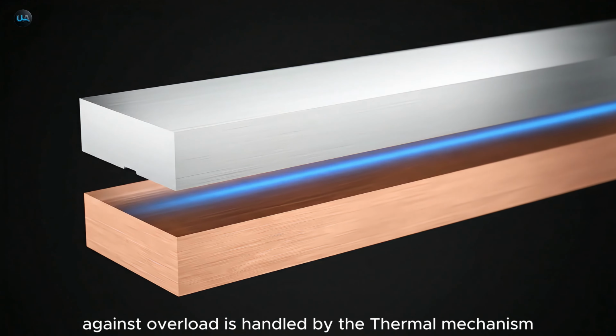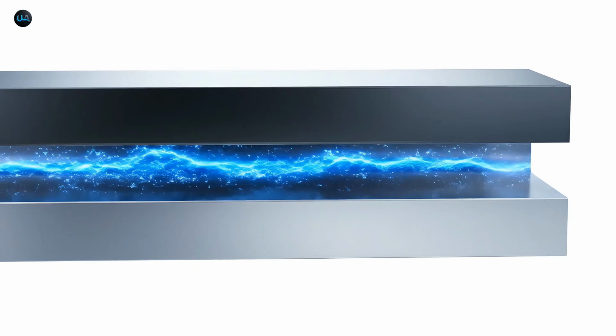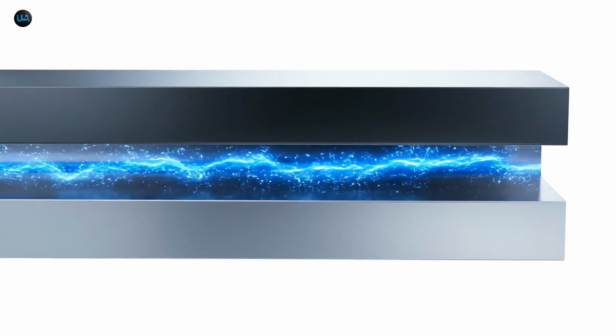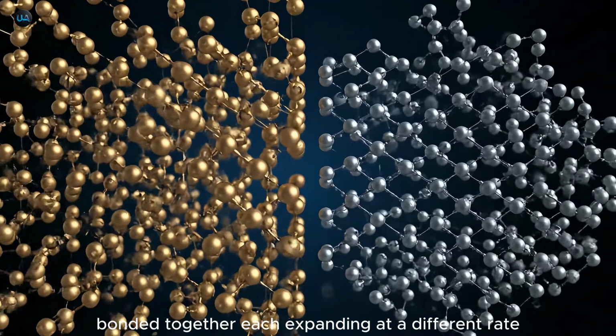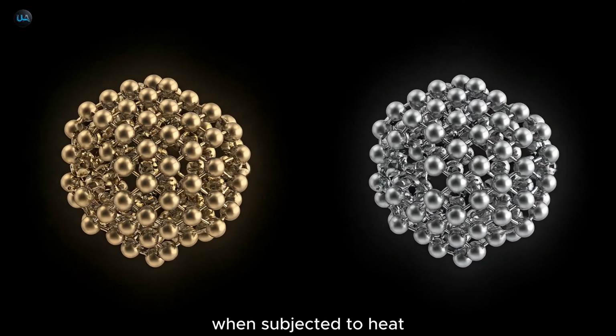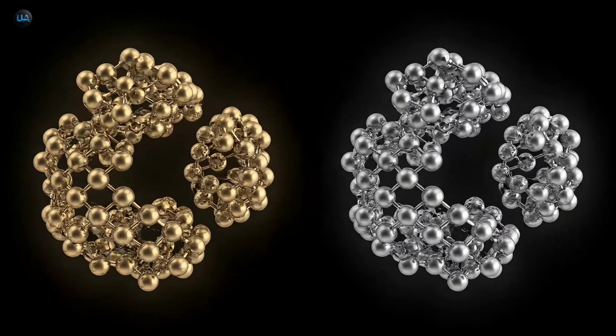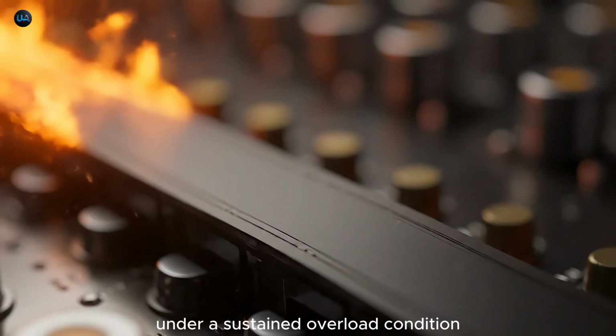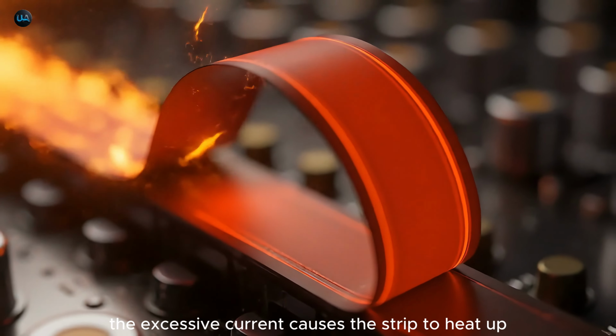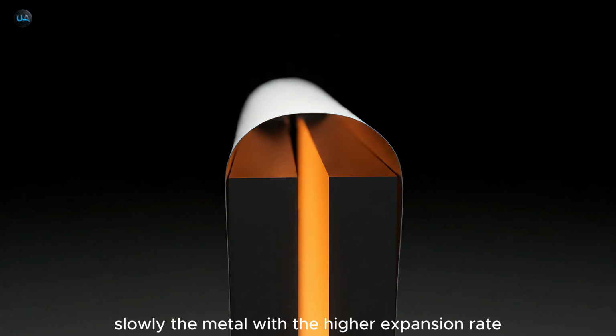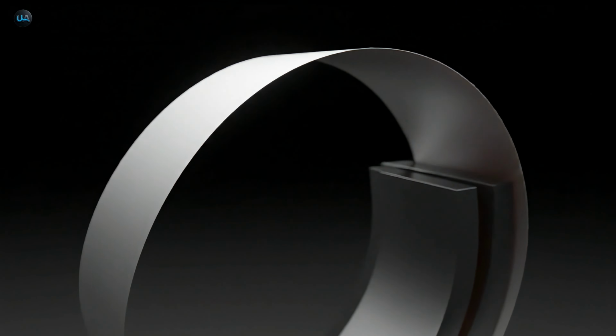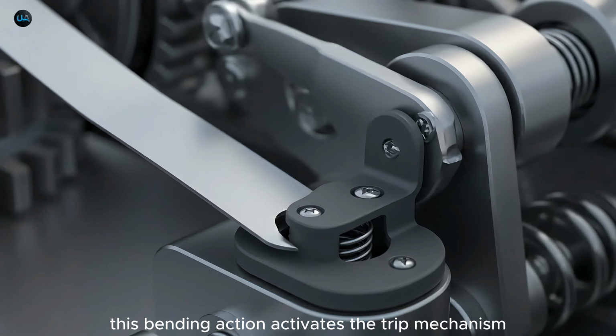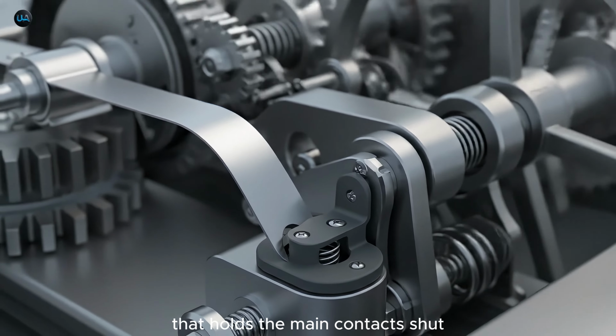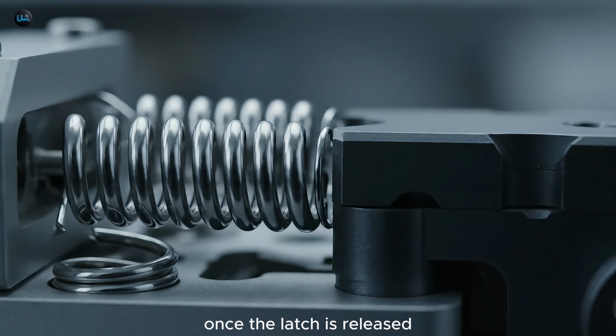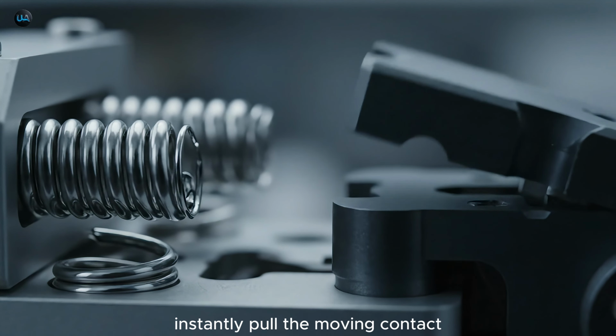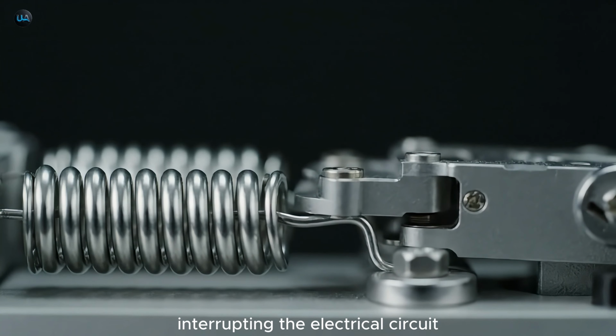Protection against overload is handled by the thermal mechanism, specifically a component known as the bimetallic strip. The strip is made of two different metals bonded together, each expanding at a different rate when subjected to heat. Under a sustained overload condition, the excessive current causes the strip to heat up slowly. The metal with the higher expansion rate forces the strip to bend. This bending action activates the trip mechanism, a precise latch system that holds the main contacts shut. Once the latch is released, powerful internal springs instantly pull the moving contact away from the fixed contact, interrupting the electrical circuit.